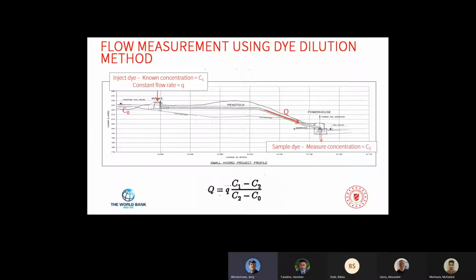So here's an image that shows just a typical power plant, and essentially the dye dilution method consists of the injection of a fluorescent dye. In this case, it's rhodamine WT, and that fluorescent dye is injected at the intake. I'm just going to point to that intake with my cursor, if you can see that. The known parameters associated with this injection of the dye is that we know exactly how much of the dye we're injecting, and we know that because we have the concentration, and we also are measuring very precisely just how much of this concentrated dye solution we're injecting.